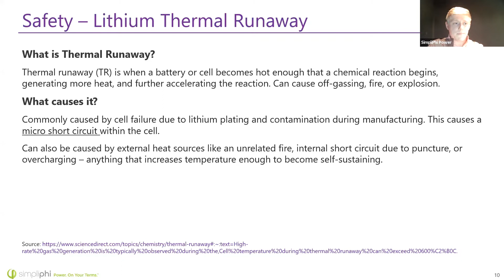This isn't a common occurrence, but when it does happen we want you to understand what happens. During thermal runaway, and only during thermal runaway, electrolyte will vaporize, creating a flammable gas. If that gas is contained within the battery cell, it will not ignite and there's no catastrophe. However, if the gas escapes the cell, it's not only toxic but also highly flammable.